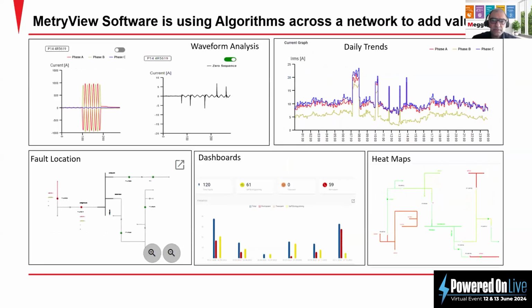These are some examples of how the MetryView software looks. The waveform analysis gives the three-phase voltage and current waveforms, plus the zero sequence for high impedance fault detection and the direction of the fault. It gives you daily graphs to get more analysis and load management.